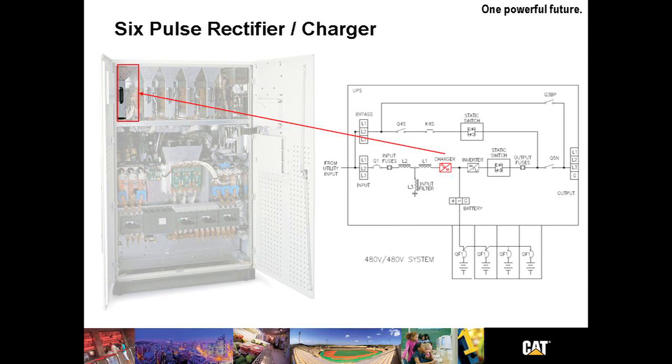Next, the 6-pulse rectifier charger converts AC to DC via 6 SCRs utilizing fully controlled rectification. The frequency of this model is 60 Hz plus or minus 10%.